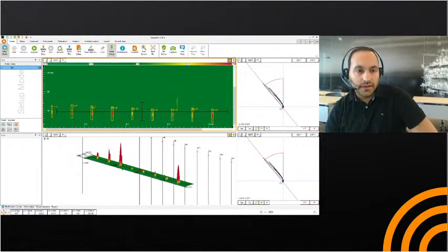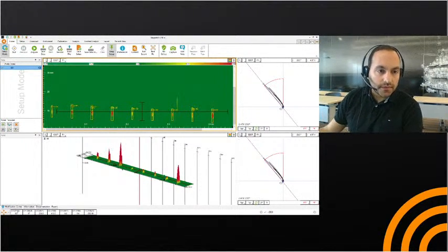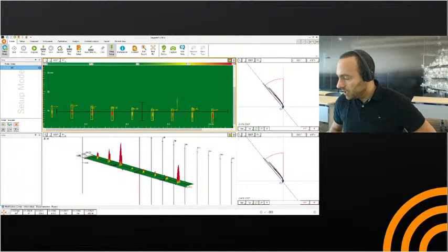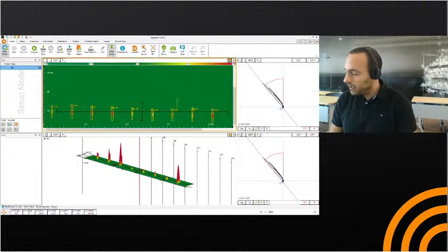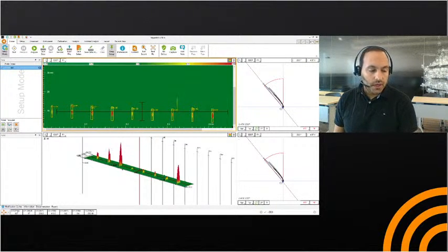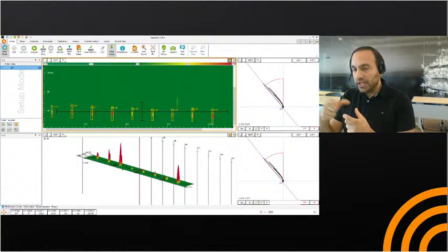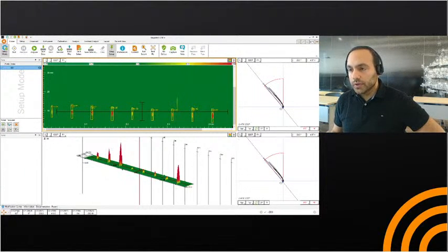All right. Let me see the next question. Here we have: what is the maximum diameter able to be used in this scanner? I just mentioned that the range this pipe scanner can take is between 42 millimeters and 170 millimeters of OD. It's actually small modules that you add to the scanner so you can cover the required OD needed.